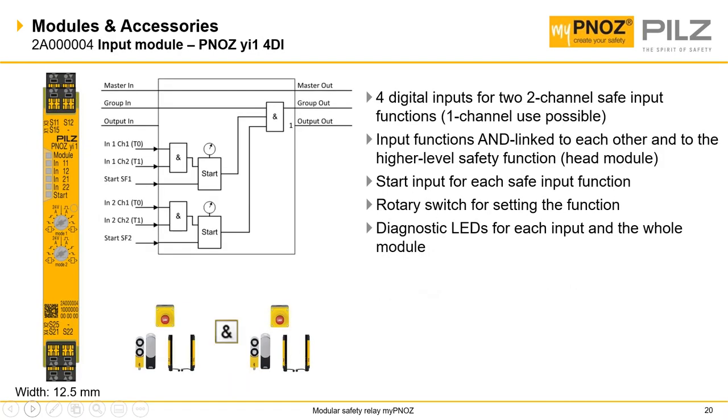The next module is the PNOZ YI1 4DI input module. This has four digital inputs that are monitoring up to two safe input functions. The input functions are AND linked to each other, as well as the higher level safety function of the head module. We have a rotary switch. And as you will find across all the 12 expansion modules, there are LED diagnostics for each individual input, output, and for the module itself.